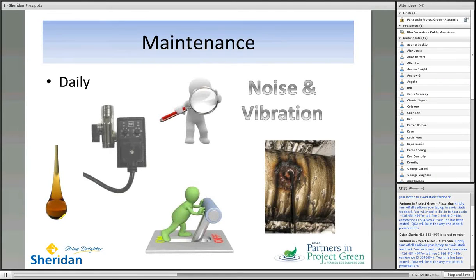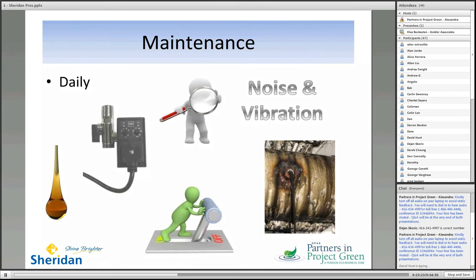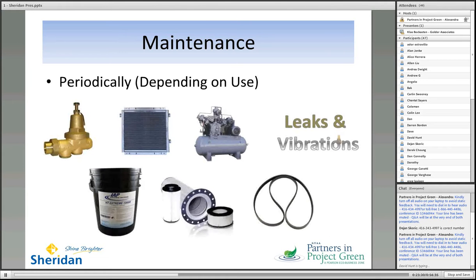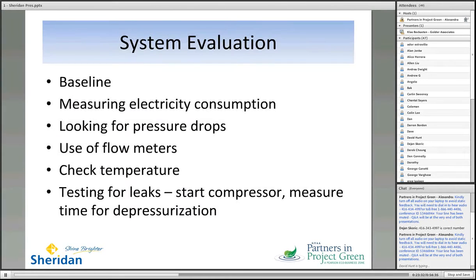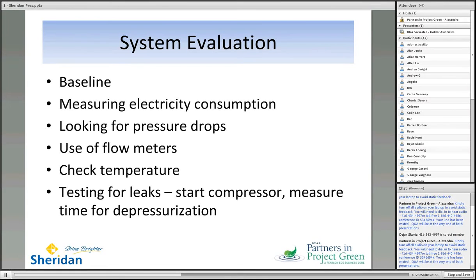And then finally, I don't know if you're able to see the slide or not, but a routine system evaluation will give you a chance to identify and perhaps catch problems early. So one thing you can do once you've leak checked your system, and you're fairly certain your end uses are good, you've looked around for pressure drops, you might want to put an ammeter on the input line to that compressor and take a look at how much electricity it's consuming. Sometime when the plant is actually offline, you may want to fill the compressor to full charge, turn it off, and see how long it takes the tank to depressurize to maybe 75% of its value. And note these things down.